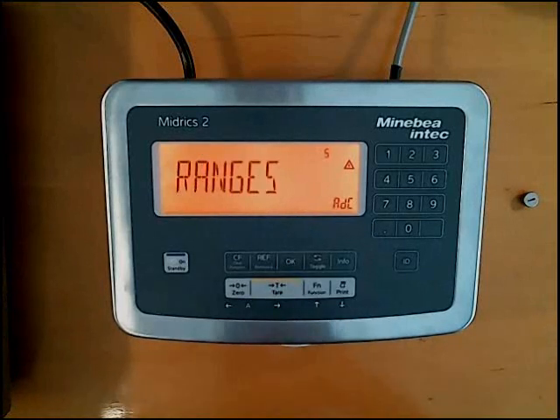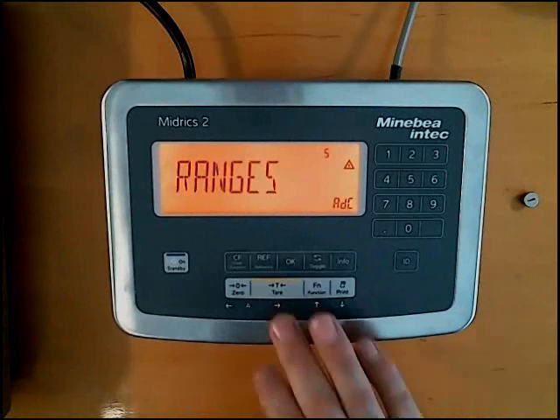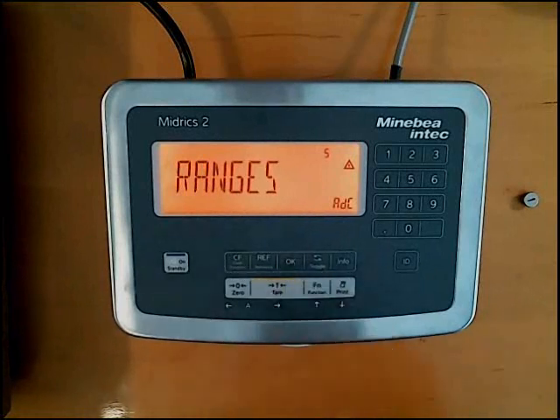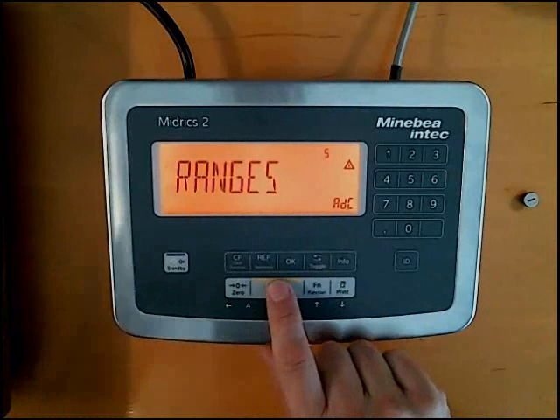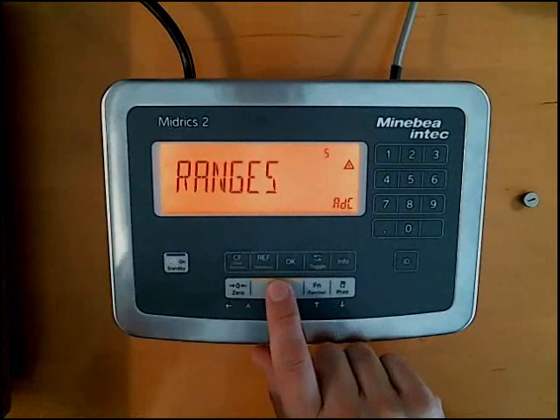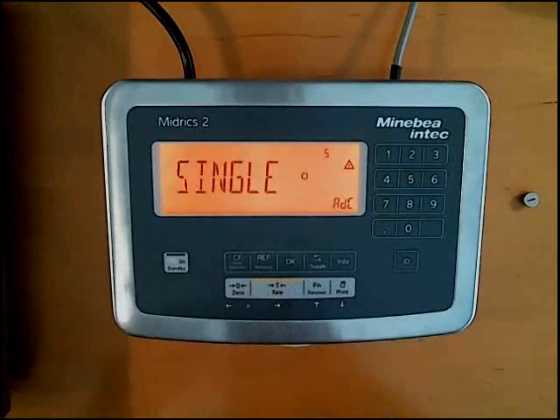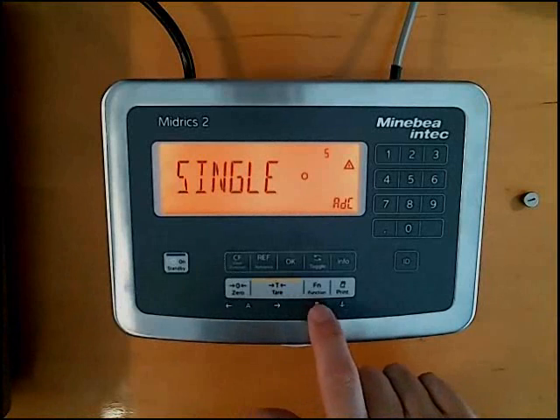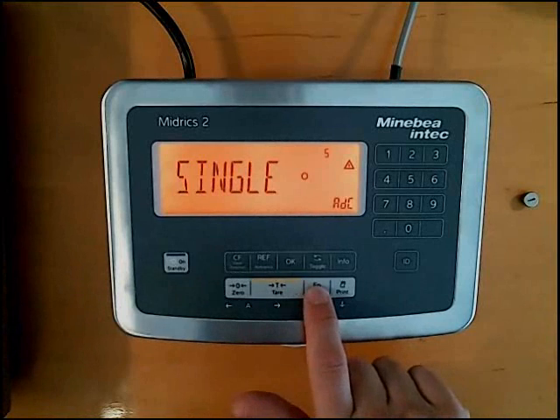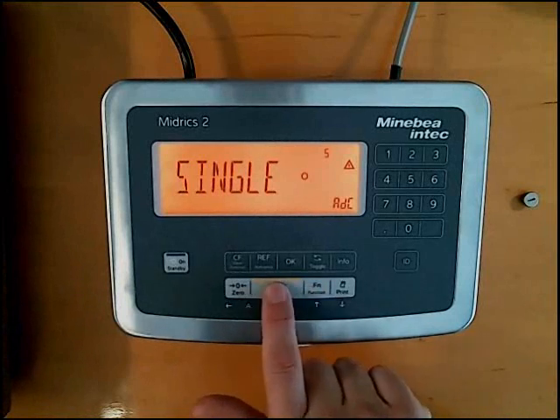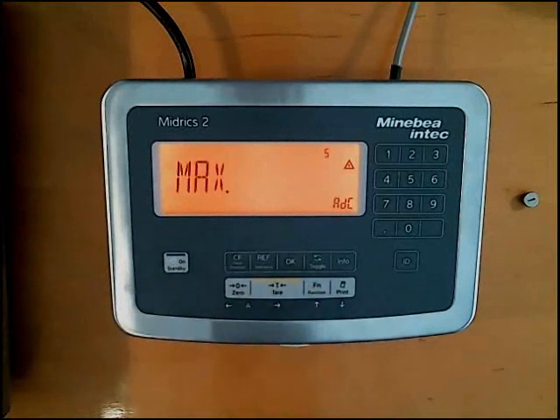The next screen that you'll see is ranges, and this is where you would change it to a multi-interval or a multi-range, but 99.9% of the time it's going to be a single range setup. So for this demonstration, I'm going to show you the single range setup. Go ahead and push tare. You'll see single, and if you want to change it, you would do so right here, but we're going to follow through with this setup. You'll see max.